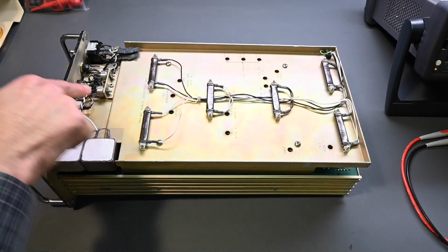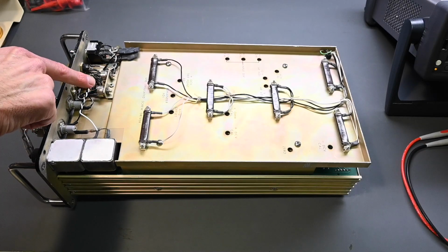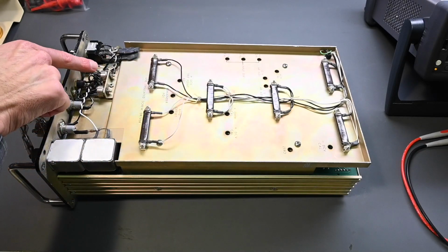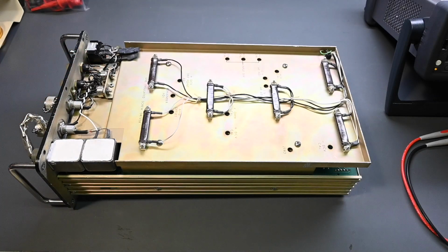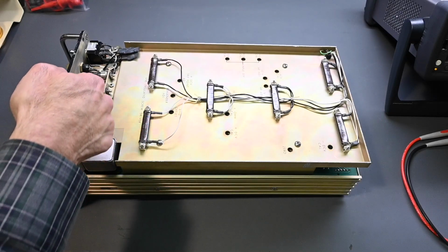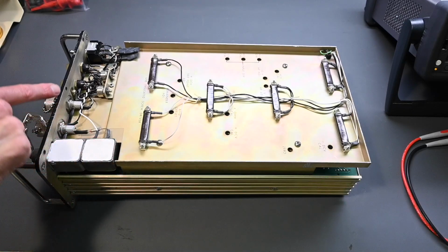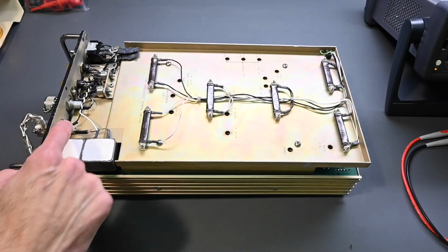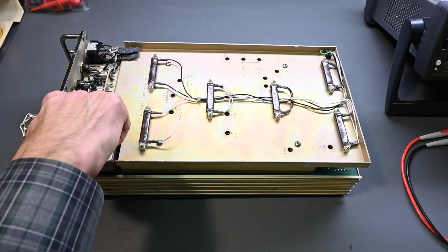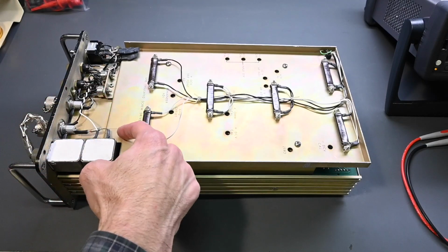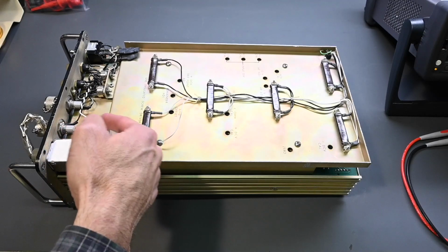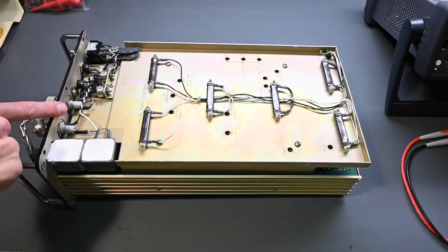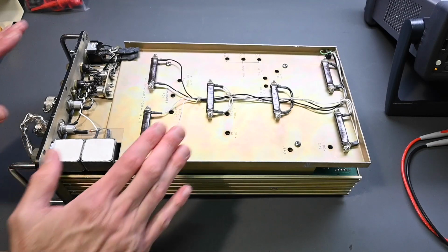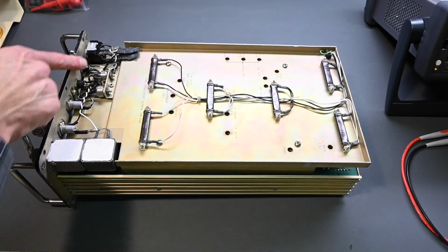And if you look right here, there's two switches. One of these is a thermal switch that controls these heaters, and the other one is a lockout so that if there's extremely cold weather, it prevents the instrument from being turned on until it actually reaches the correct operating temperature. And this panel right here where it comes up underneath these fuse holders is a very close fit, and there's a metal ring on each fuse holder where the wiring attaches, a very, very close fit under there, and there's an insulated piece that's adhered to this panel, another insulated piece right here, so it's AC line coming in right there. But everything clears correctly, very, very close fit. So if you are working on one of these instruments, make sure that nothing shorts out in this area up here.